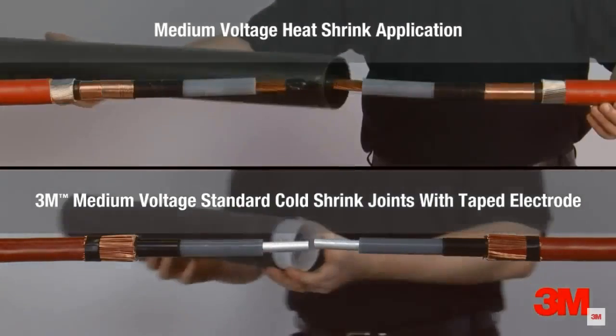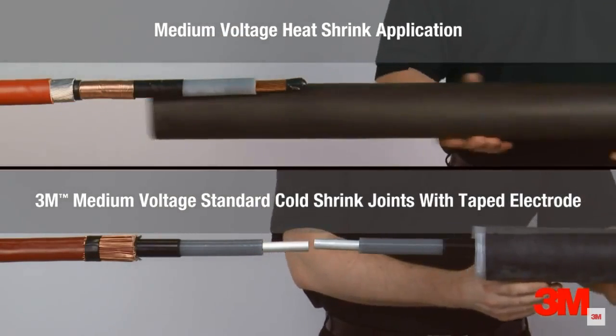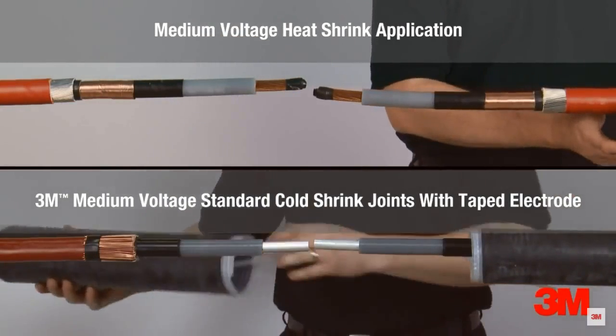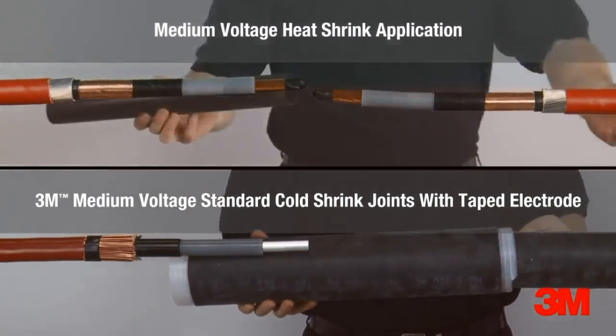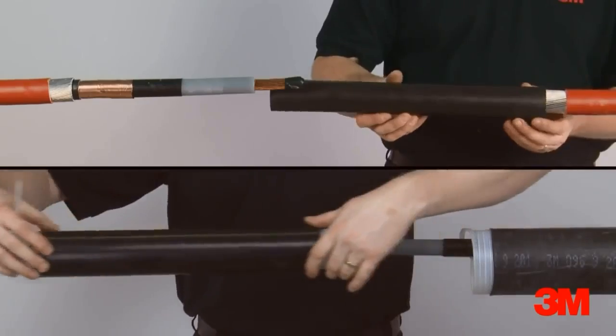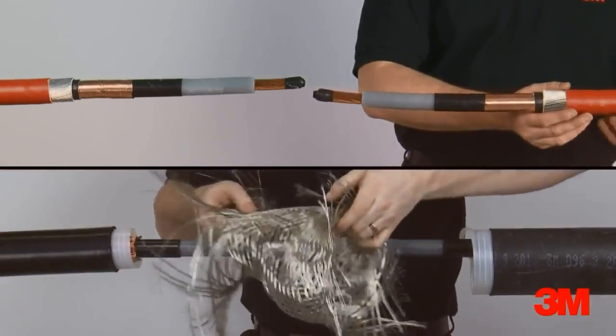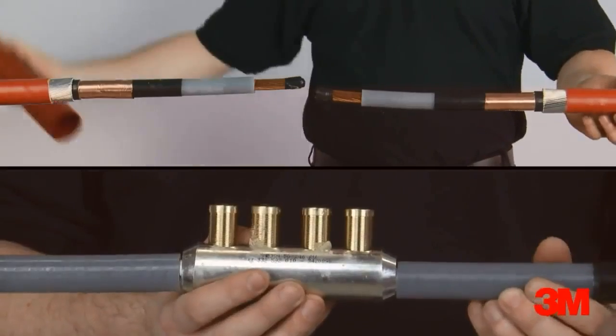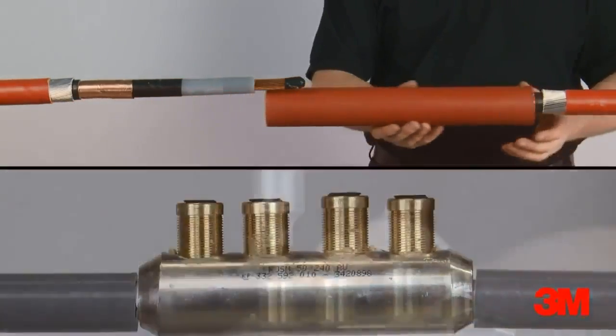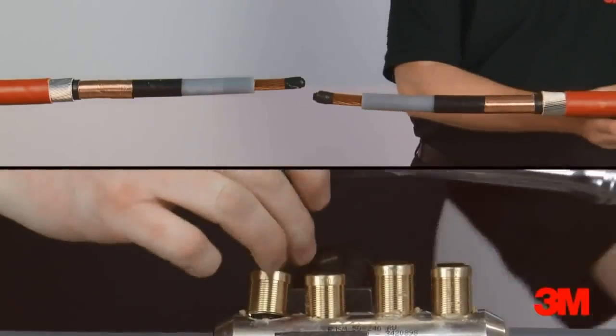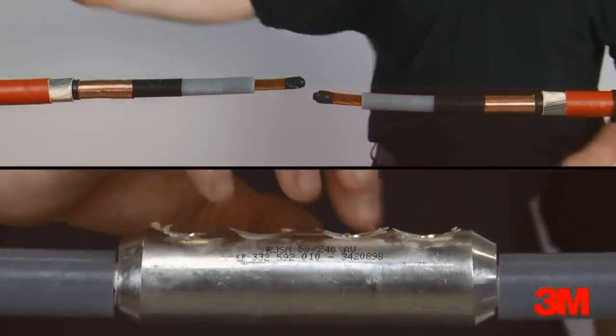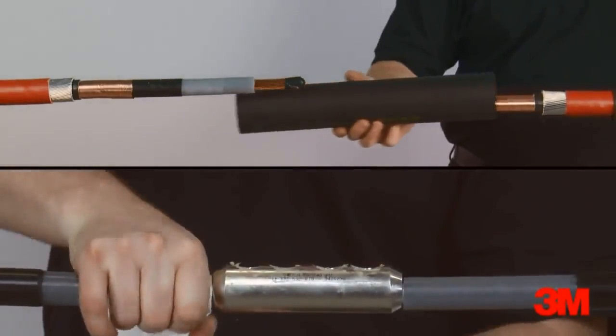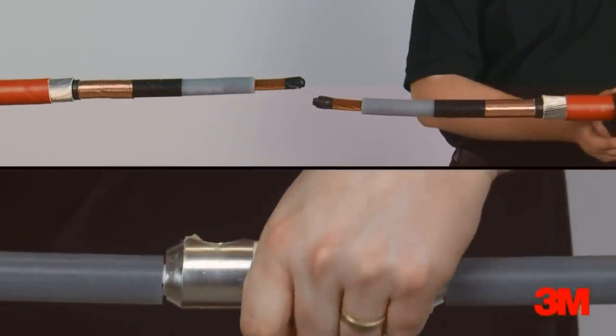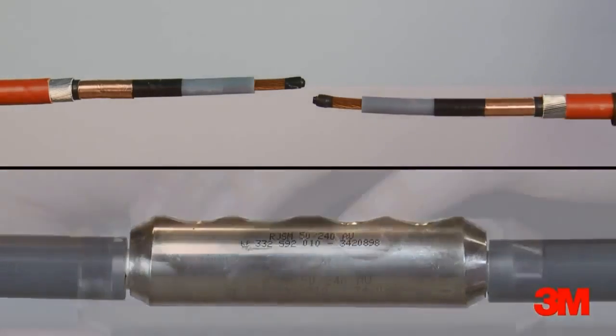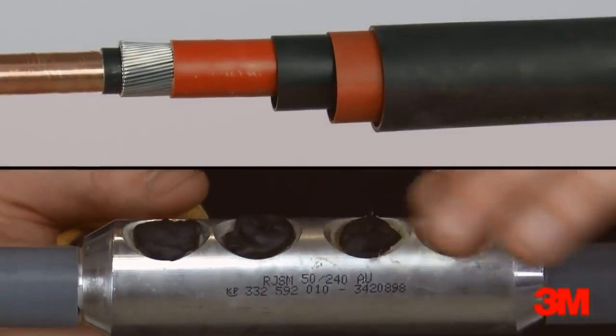3M standard cold shrink tape electrode joint offers a viable cost-based alternative to heat shrink cable jointing technology and allows for a reduction in installation steps. Unlike heat shrink alternatives, a molecular permanent set ensures constant radial pressure is exerted on the cable for the duration of the cable joint's life. Unlike the individual layers that are necessary for a heat shrink joint, which must be allowed to cool sufficiently before the next layer can be applied, 3M cold shrink splice bodies contain all the necessary layers in one component. Any additional cold shrink layers, such as our outer protection tube, can be applied immediately.